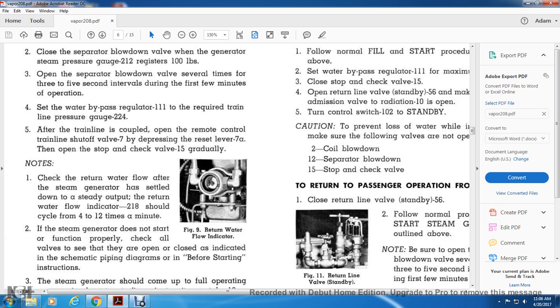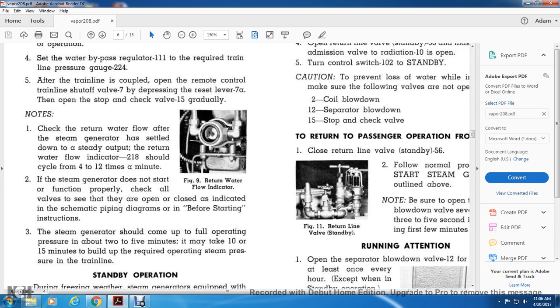2. The steam generator does not function properly. Check all the valves to see that they are open or closed as indicated in the schematic piping drawings before starting. The steam generator should come up to full operating pressure in about 2 to 5 minutes. It may take 10 to 15 minutes to build up the required operating steam pressure in the train line.